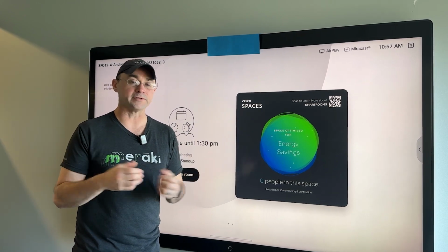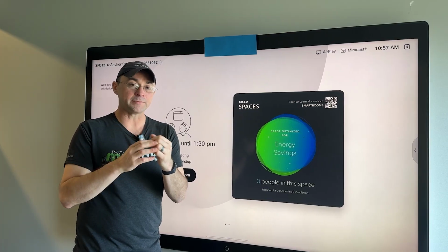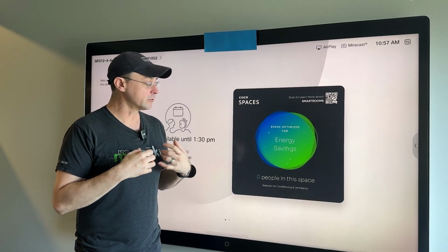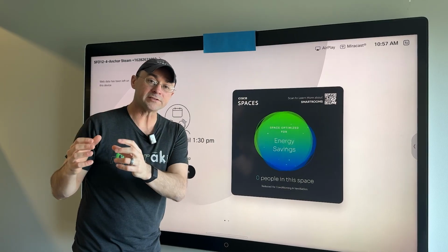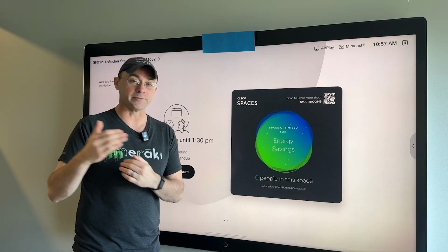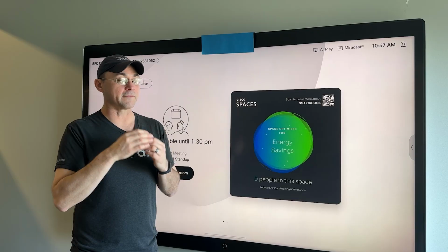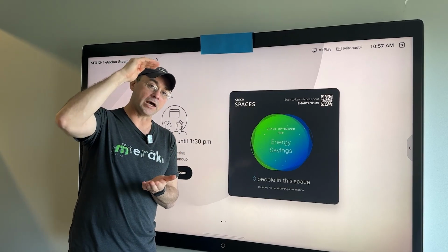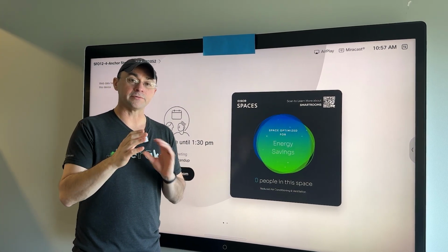And what we're able to do is in the zones and in the rooms, they have something called set points. And effectively what it means is the temperature needs to be maintained between a lower bound and an upper bound. So since we know the occupancy, since we know when meetings are happening, that enables us to be intelligent to precondition the rooms or to condition them on demand. Given that information, most customers are very comfortable with decreasing that lower boundary and increasing the upper boundary so the HVAC doesn't have to work as hard to be in between there.